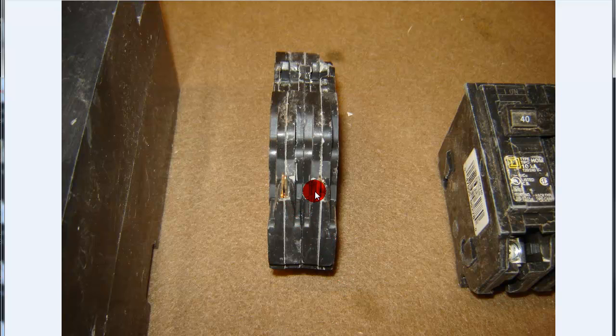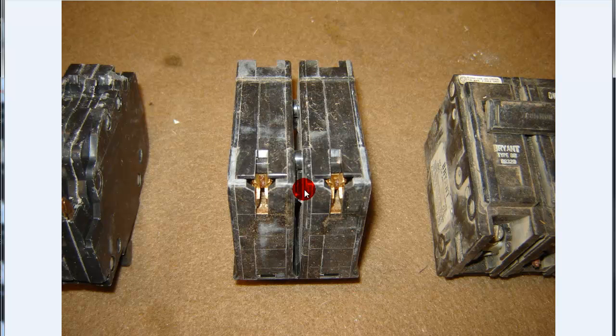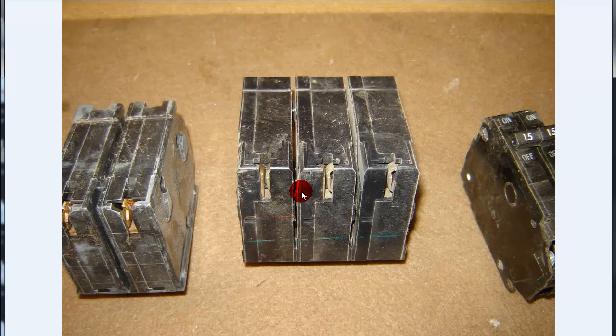This is the old FPE Stab-Lok. I don't think you can buy those anymore — they have a new replacement breaker for those that's supposed to be UL listed. But bad boys, that's old. There's another ITE. Whenever you're replacing these, you need to make sure that you replace like for like — I'll talk that one to death. Even though those are two different types of breakers, the depth of these, the width of the slots — they're all different. You've got to pay attention to that stuff.